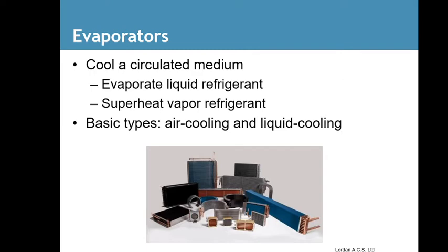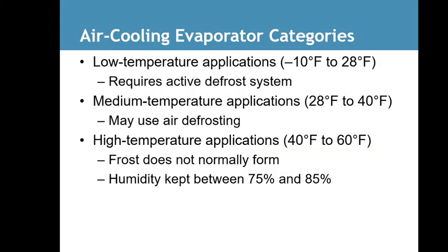Evaporators cool a circulated medium, evaporate liquid refrigerant, and superheat vapor refrigerant. Basic types are air-cooled and liquid-cooled. Air cooling evaporator categories: low temperature applications, -10 to 28. That's usually a freezer.